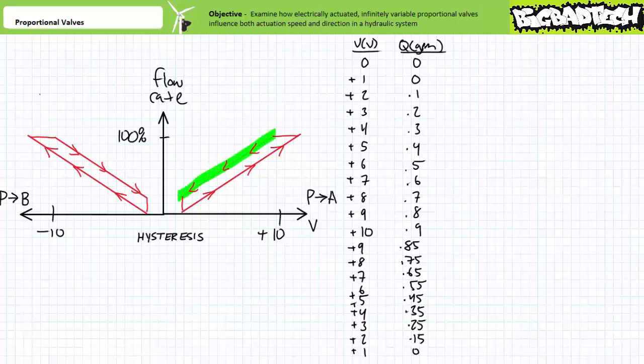When plotted on the way down, the flow rate as a function of applied voltage would look like the highlighted curve. This phenomenon is known as hysteresis and has everything to do with the magnetic friction I referred to earlier. Regular friction and oil impurities also play a part.